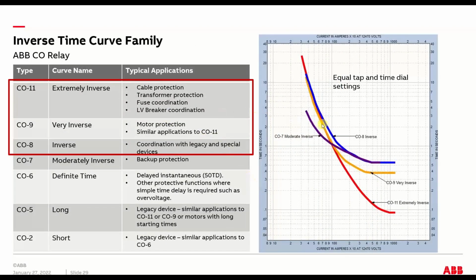Here's the curve family that's pretty typical for relays. There were all these model numbers dependent upon which manufacturer you had. ABB/Westinghouse called them CO, and then gave them a number at the end. GE was IAC with a number. But then they had these terms like extremely inverse, very inverse, inverse, moderately inverse. The terms are sort of what the curve is, but they're not consistent across manufacturers.